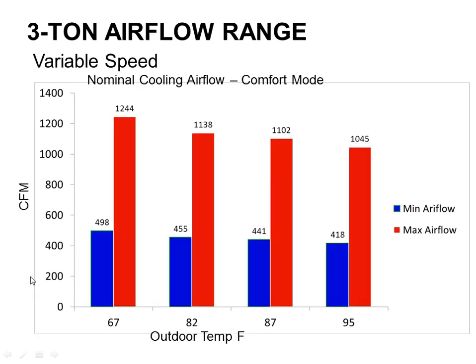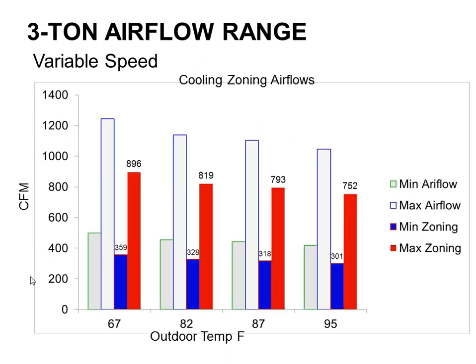We'll look at one of these variable speed Bryant Extreme or Carrier Greenspeed heat pumps. It's a much different story. I'm able to ramp this guy down much further on the compressor side, so therefore I can ramp him down much further on the indoor unit's airflow side. So in this case, for a 3-ton unit, I'm able to reduce him down about 60%. So instead of cutting his airflow back 20%, I can reduce it 60%. That ends up saving me a couple hundred dollars extra a year on fan energy. In addition, it allows me to work very well with zoning systems, which we'll talk about in a second here.